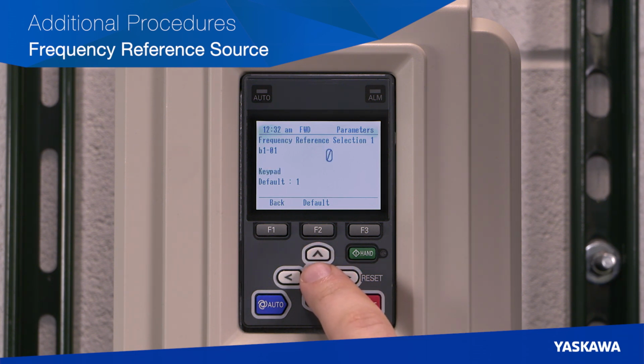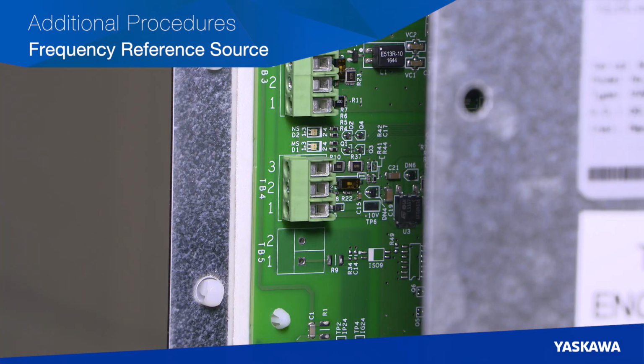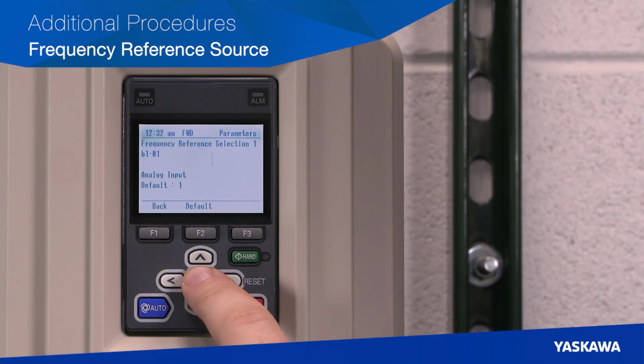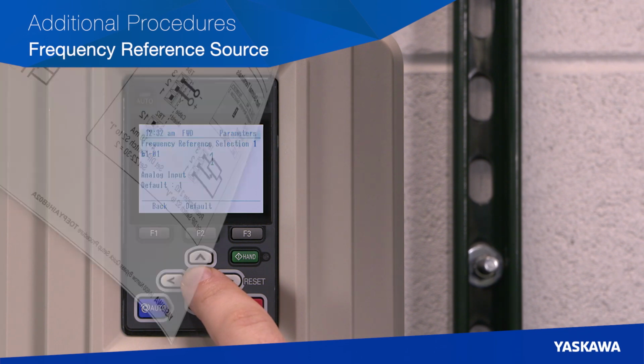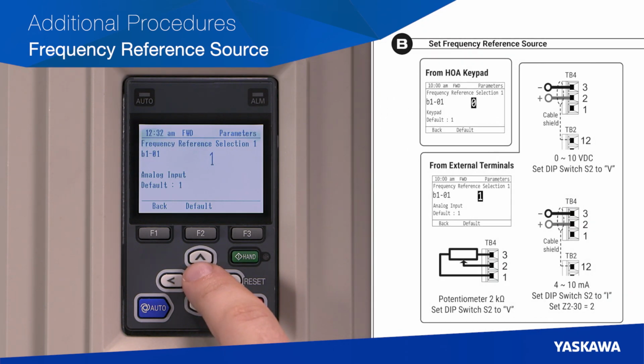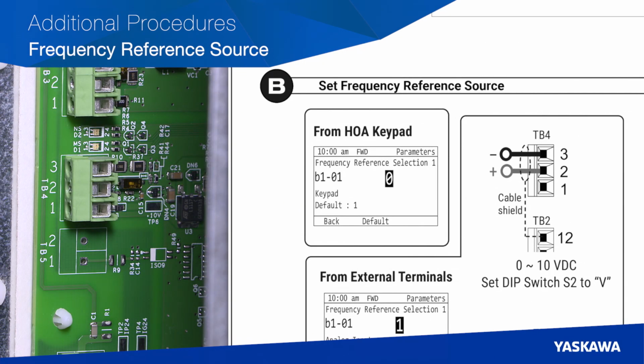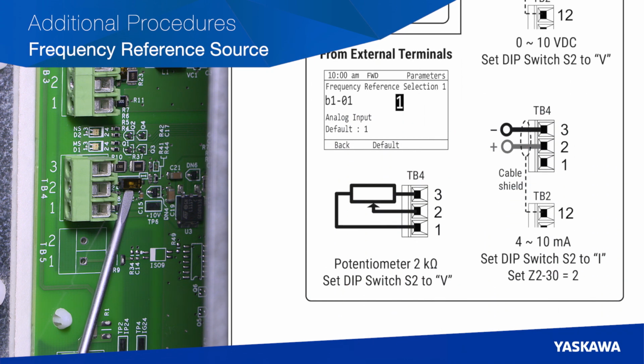Popular settings include a setting of 0, the keypad. The speed can now be adjusted by pressing Enter on the Home menu while running in auto drive mode. Or choose a setting of 1, analog input. This uses the TB4 terminal on the bypass control board. This can use a voltage or current source signal for the frequency reference. See the quick startup procedure for wiring diagrams on the subject. And don't forget to adjust the S2 dip switch to V for voltage signal or I for a current signal, along with parameters Z2-30 equals 2, if applicable.